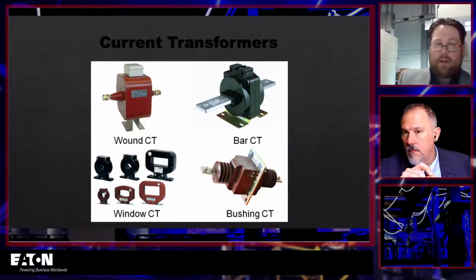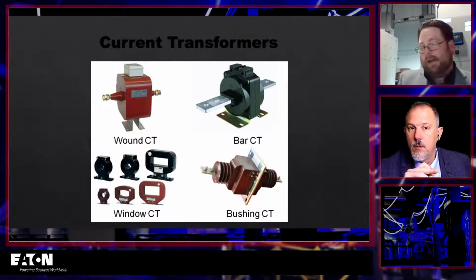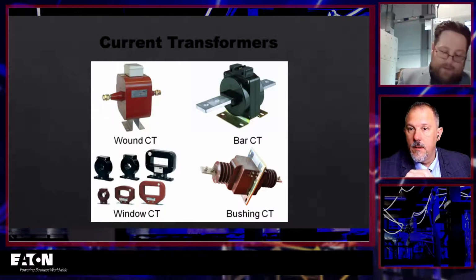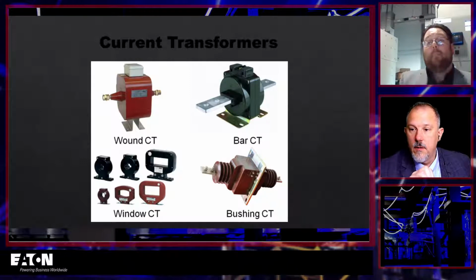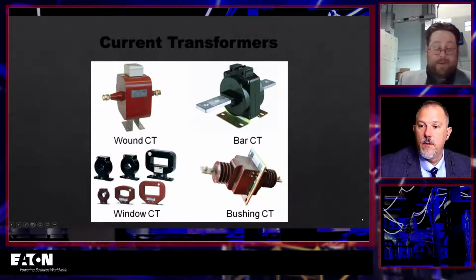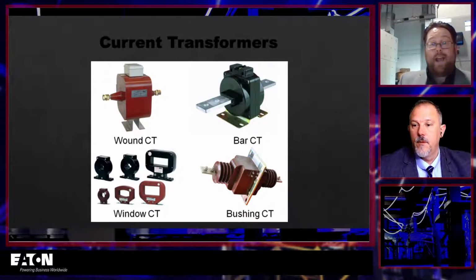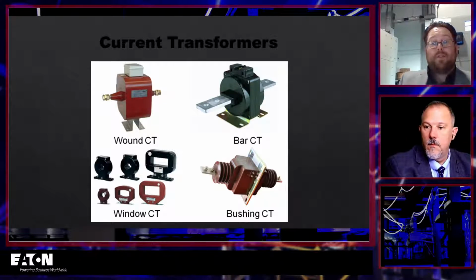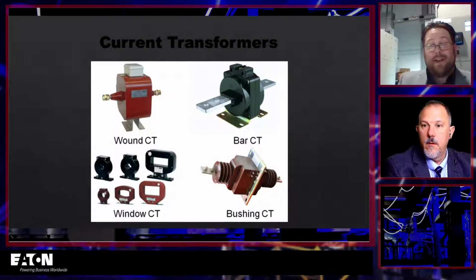So number one, we'd be looking at the nameplate. There's going to be a nameplate on here that tells you the ratio. Now, in the old days, it was painted on or written with a marker, so you probably can't see it anymore. But as part of startup, commissioning, and maintenance, on any transformer we should be doing a turns ratio test. That's actually a very simple little test, and a lot of them are handheld nowadays.